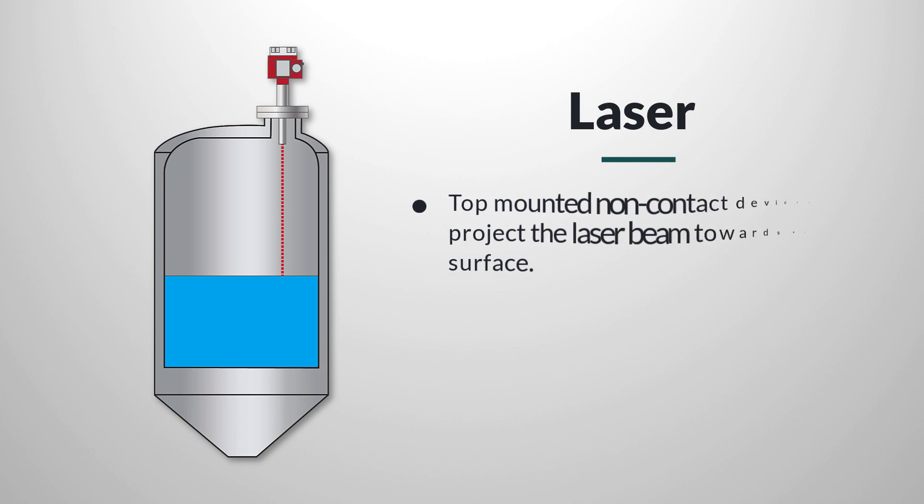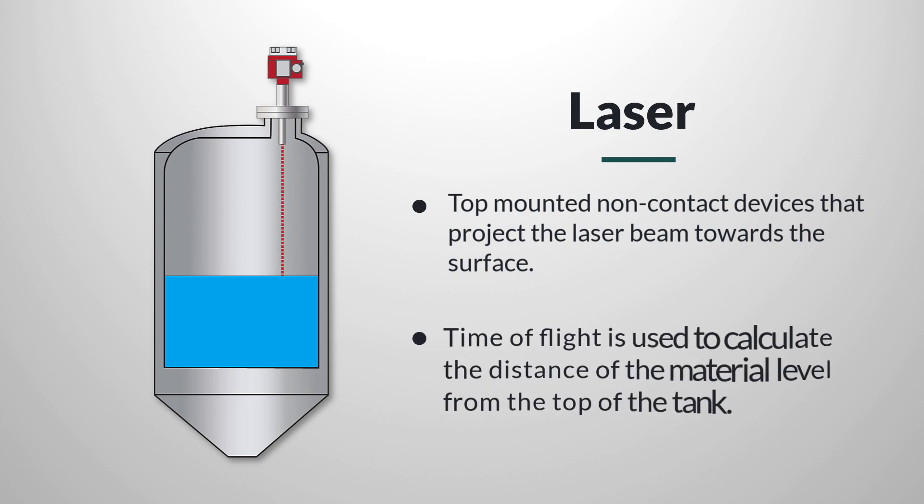Laser level is a relatively uncommon technology that shows increasing promise for certain difficult applications. Laser level gauges are top-mounted, non-contact devices that project the laser beam toward the surface. Time of flight is used to calculate the distance of the material level from the top of the tank.